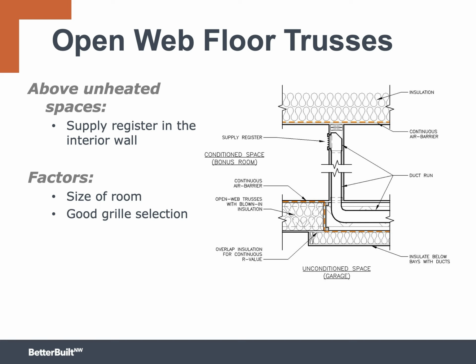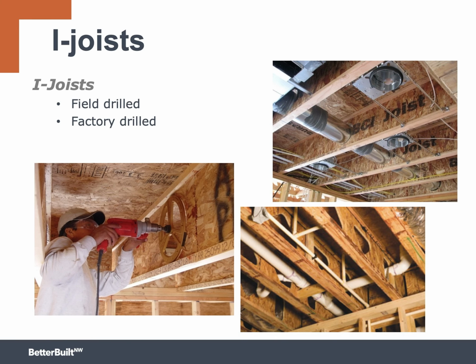Another approach for getting air into the living space above the garage is just to avoid the issue altogether, by not running the duct in the floor out to the perimeter. Instead, run the duct up into the wall that separates that living space from the main body of the building. In this drawing, you can see that the duct just runs up the wall and ends near the ceiling. Air shoots out into the room. The success of this is going to depend on how big the room is, but also how much throw you have in that register and what kind of grill you put on that register.